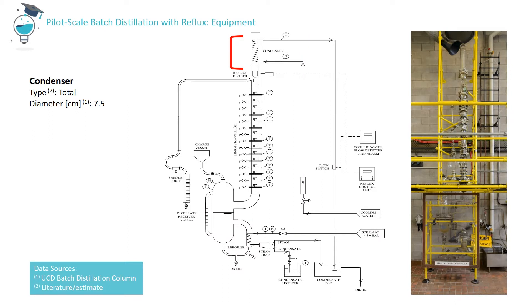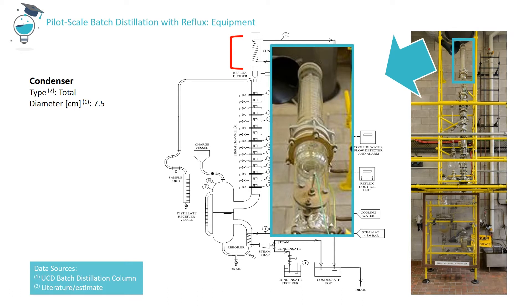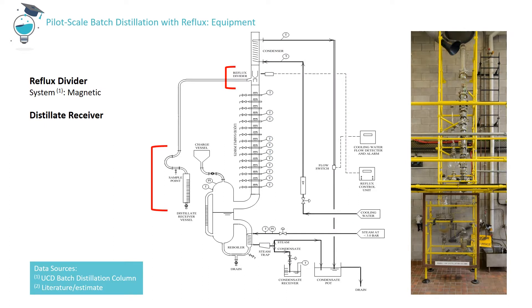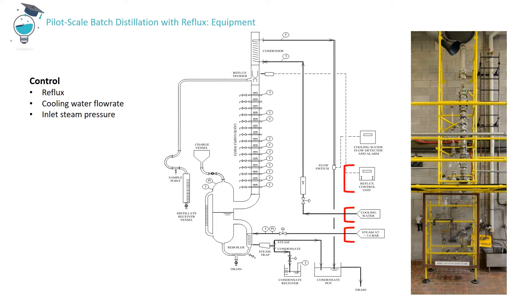At the top of the column there is a water-cooled condenser with an internal diameter of 7.5 centimetres. Just below the condenser is the magnetic reflux divider. Based on the specified reflux ratio it diverts the distillate from the condenser either to the distillate receiver or back to the column as reflux. To operate the column in total reflux — i.e. returning all condensate to the column — the magnet is inactive. The reflux controller is used to specify the reflux conditions, either total reflux or a finite value of reflux ratio. The cooling water flow rate can be manually adjusted using the cooling water valve. For safety reasons the system is equipped with a cooling water alarm which sounds if the water flow falls below a specified limit.